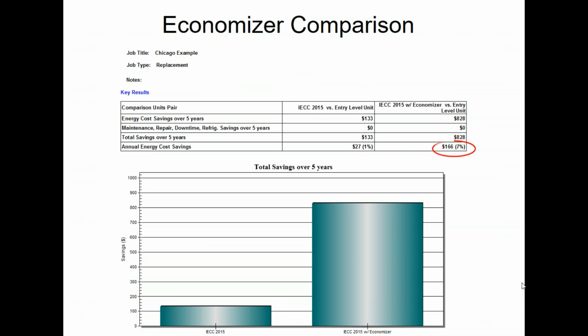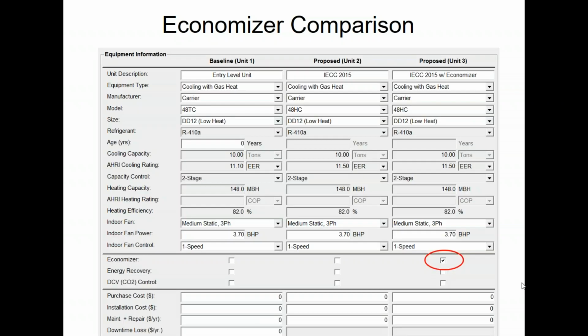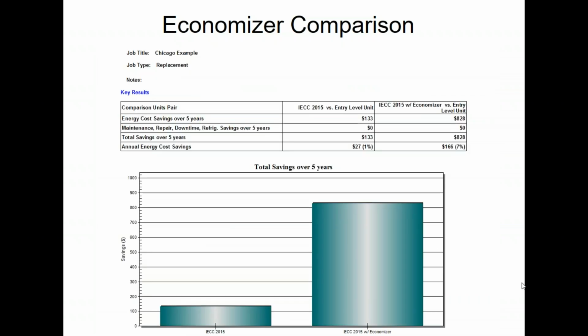So if you look at the energy savings, going from an entry-level unit to a code-compliant unit saves me 1%, or in the case of this example, on a 10-ton unit, saved me $27 a year. If I put the economizer on, it saves me 7%. So the economizer is getting me quite a bit of energy savings above and beyond what just having an efficient unit might.